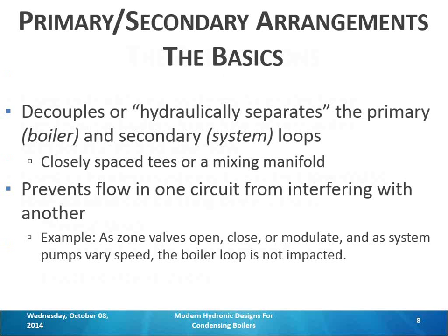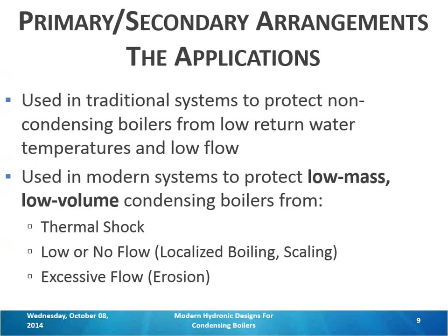If you begin to condense in a cast iron or Scotch Marine style boiler, you're going to be replacing tubes or sections over time as it corrodes away that material. So typically the designs would be 140 Fahrenheit minimum, but usually you would see 160 return to 180 outlet. And that gives you enough of a buffer where if something goes wrong, you're not going to condense inside that boiler.